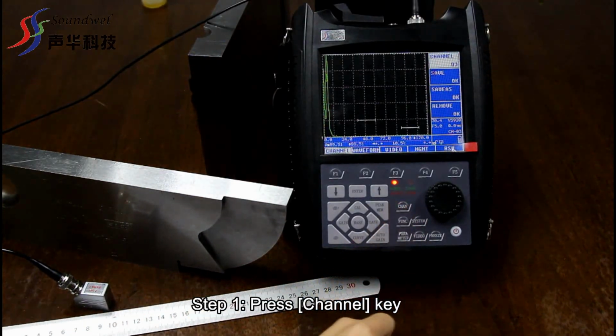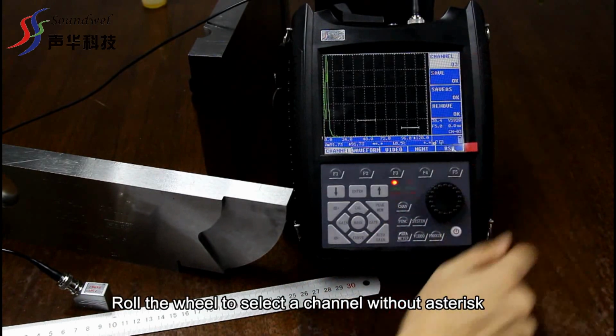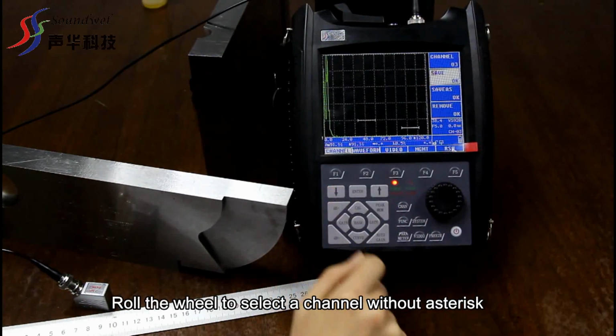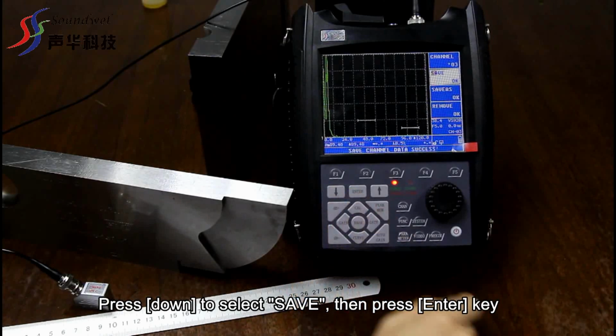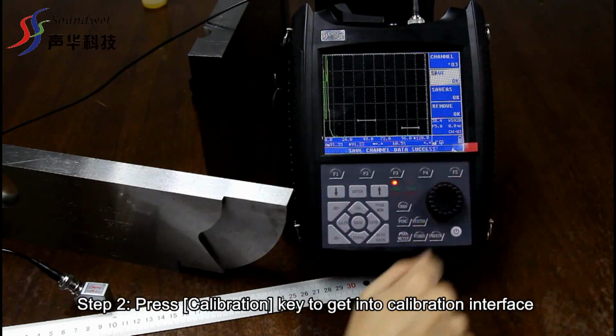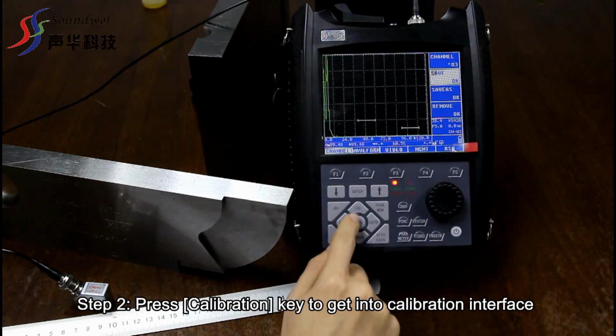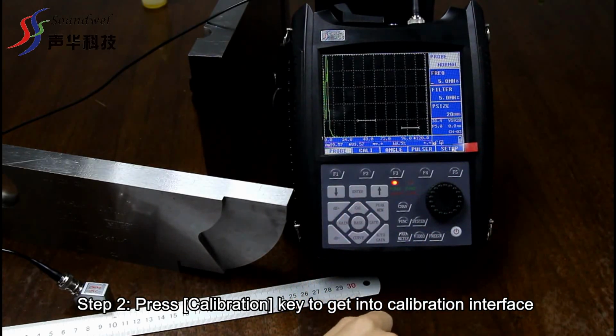Step 1. Press Channel key. Roll the wheel to select a channel without asterisk. Press down to select Save, then press Enter key. Step 2. Press Calibration key to get into Calibration interface.